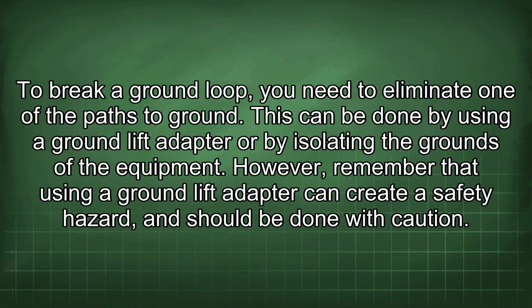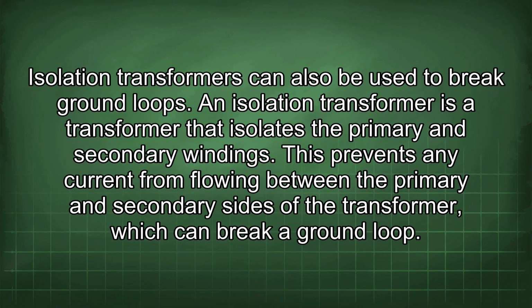To break a ground loop, you need to eliminate one of the paths to ground. This can be done by using a ground lift adapter or by isolating the grounds of the equipment. However, remember that using a ground lift adapter can create a safety hazard and should be done with caution. Isolation transformers can also be used to break ground loops.